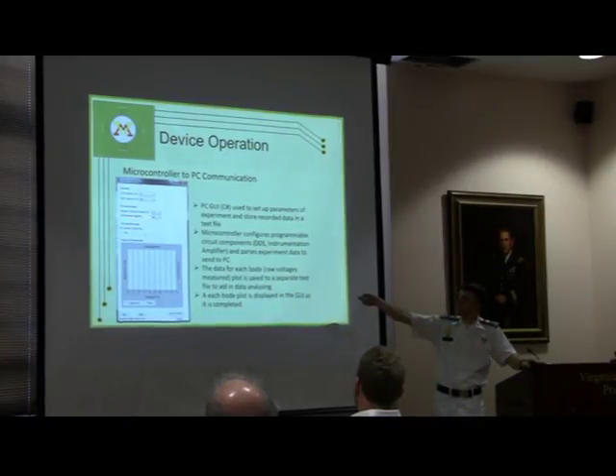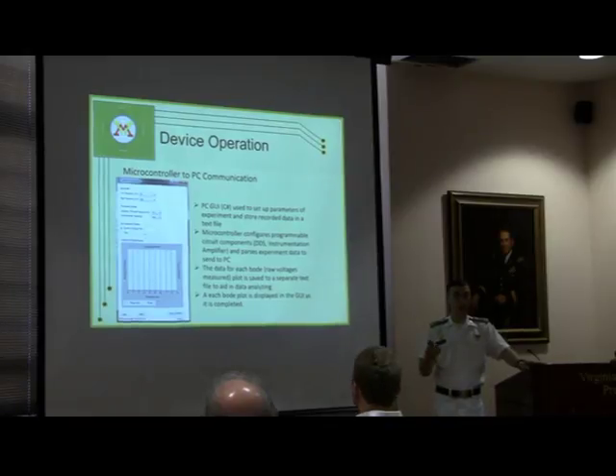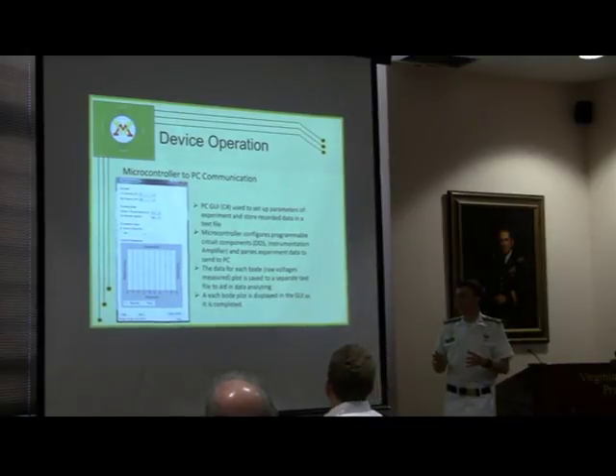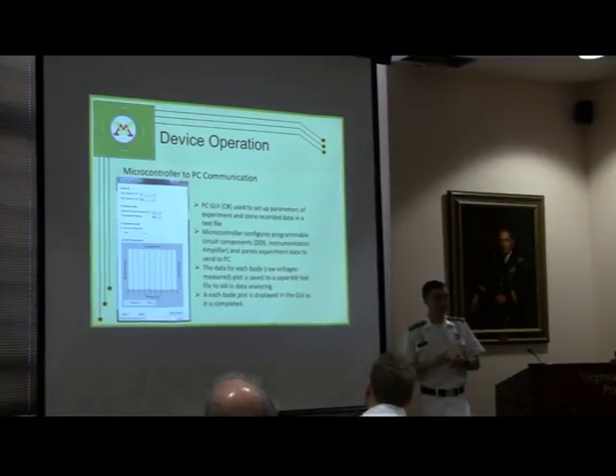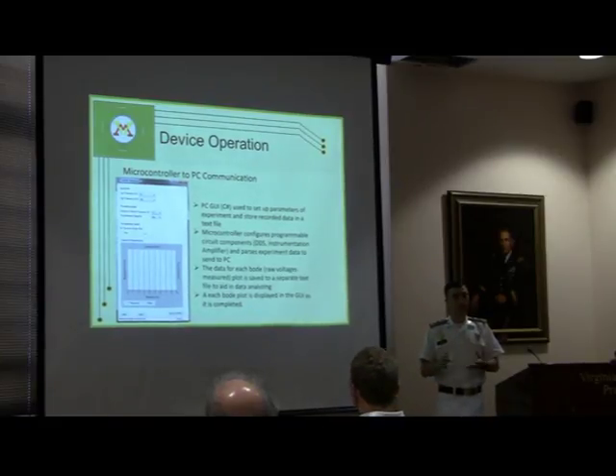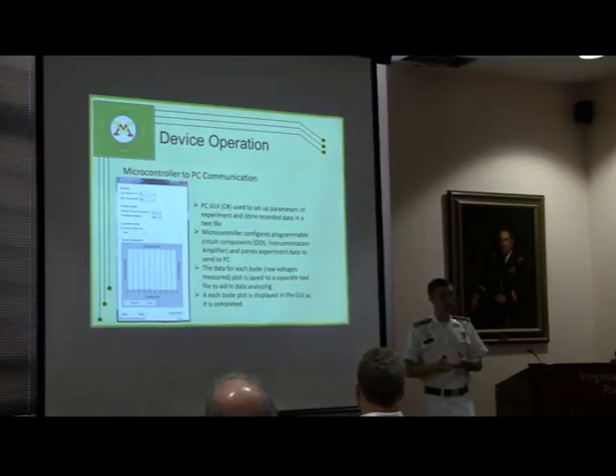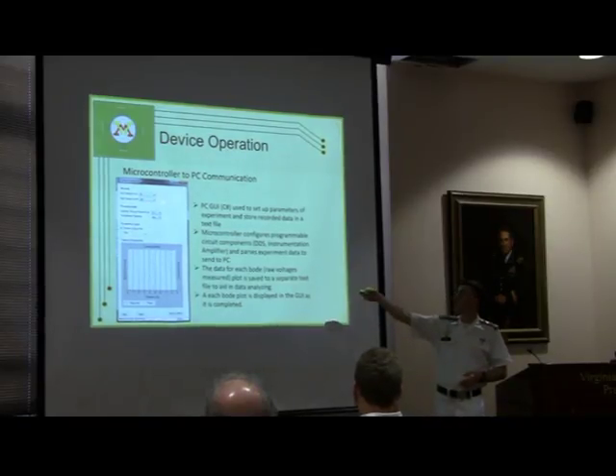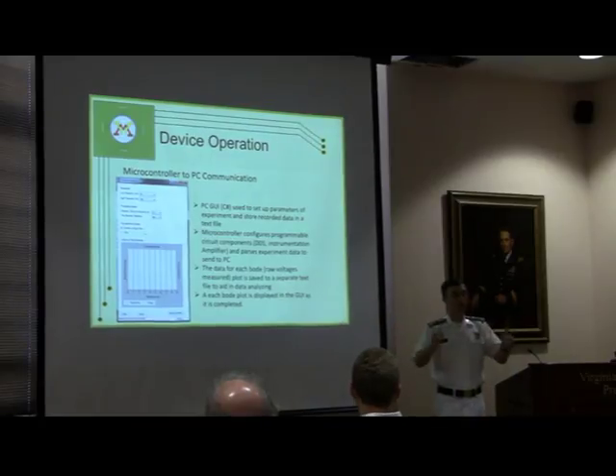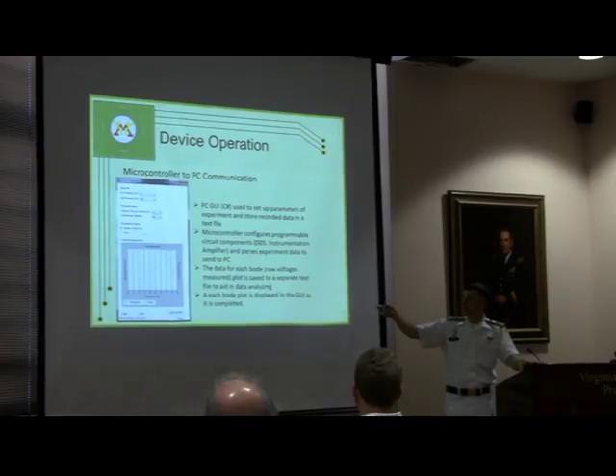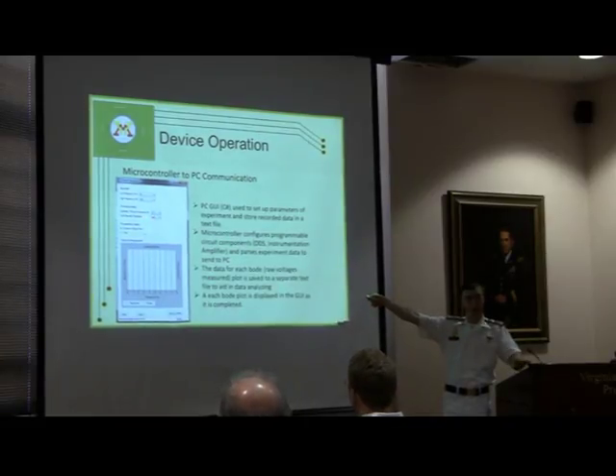This control right here selects how long you wait between completing a Bode plot to take another reading. So what you're building essentially is a series of Bode plots, and this shows the magnitude and the phase of the voltage waveform that you're reading across a range of frequencies. So the range of frequencies you select in here, all that is for one Bode plot. So it does all those readings for one Bode plot, and then if you wanted to do more Bode plots, you specify that there, and it'll move on to the next one. So this control is selecting how long you wait before you move on to the next Bode plot.